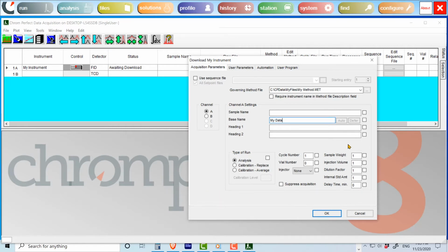The method file determines how the acquired data files are processed. In a single-channel instrument, the only channel is channel A, which is processed according to the governing method file. In a multi-channel instrument, the several channels represent data from different detectors, if not different columns. The responses and even the retention times may be different, so each channel needs its own method and calibration files. Therefore, the other channels require the name of a processing method file, which names the appropriate calibration file for that channel. Each channel also requires its own base file name, so you can identify the different files associated with each detector.